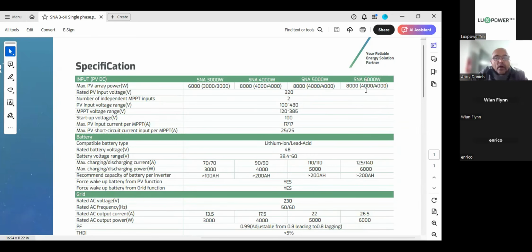In no instance can you exceed, in your combined power, remember that solar panels are installed in series, all right? So if you're putting up a 500 watt panel, it'll be 4,000 divided by 500. That means 8 panels per string. But the next thing we need to do, now that we know we cannot go over 4,000 watts per input, we can't exceed 8. Then we look at the open circuit voltage rating of the panel. That will be on the information sticker which comes with the panel. And it might be 48 volt or 52 volt, depending on how many cells it has. You get 72 cell, you get the old 60 cell, and even now we get the 144 split cell. So you have a look at the VOC. That is open circuit voltage. I'm sure you understand what open circuit voltage means. It means exactly that.